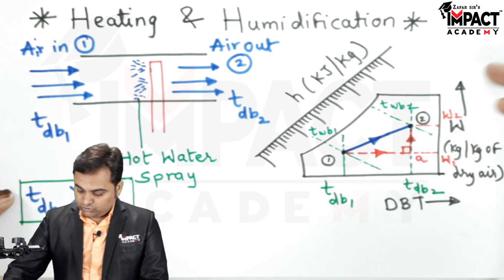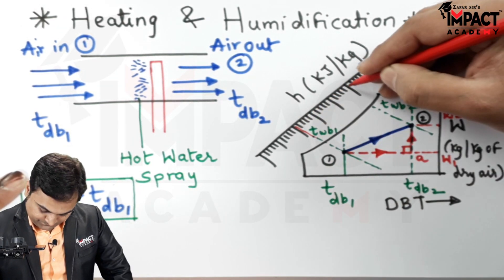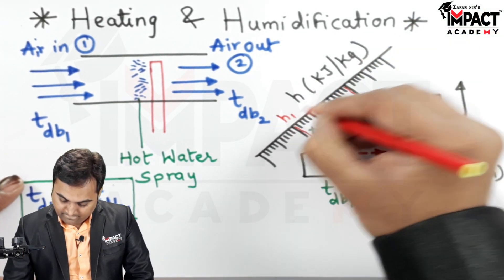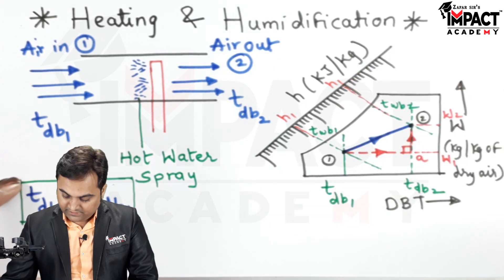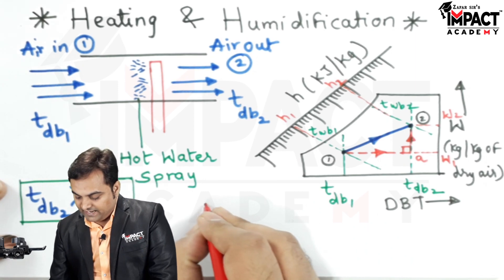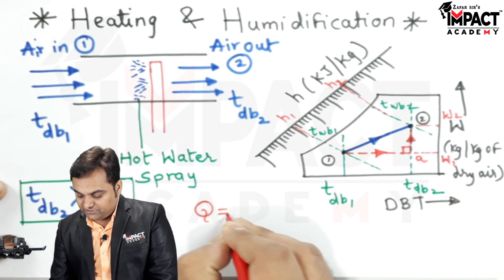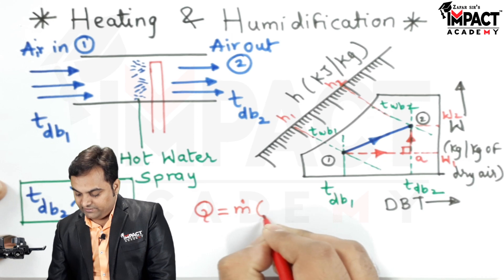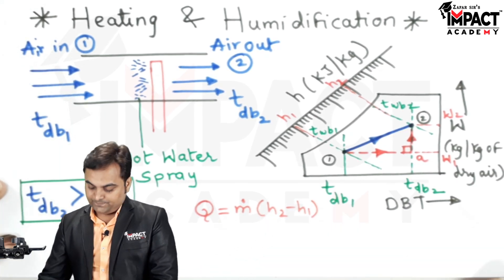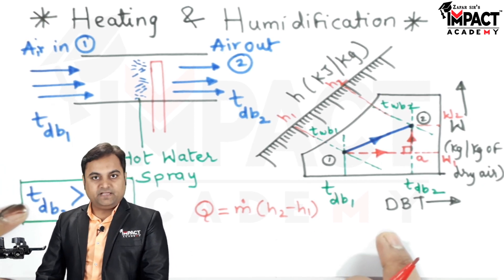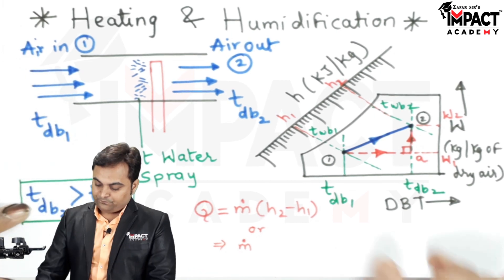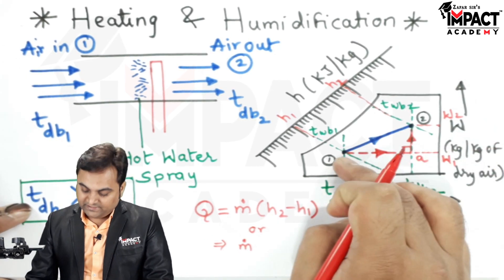To find the enthalpy, plotting points 1 and 2 on the specific enthalpy scale gives us h1 and h2. The total heat added during heating and humidification is given by the mass flow rate of air multiplied by the enthalpy difference: Q = ṁ × (h2 − h1). This can also be written as ṁ × (ha − h1) for the sensible heating component.